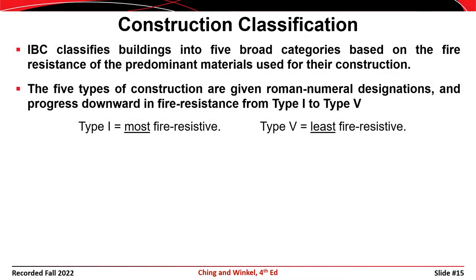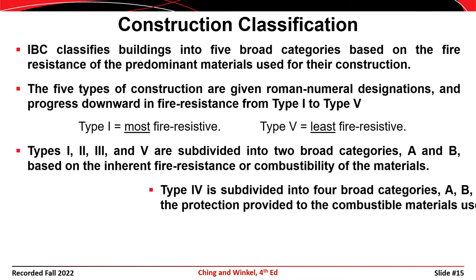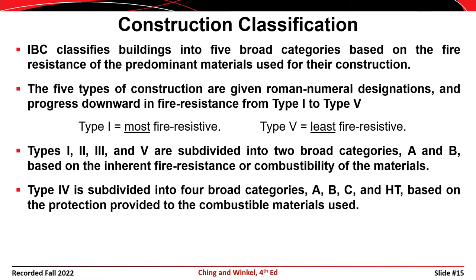The International Building Code includes five major types of construction, Types 1 through 5, with Type 1 being the most resistant to fire and Type 5 being the least resistant to fire. Each of these five main types is further subdivided into an A or B classification, except that Type 4 is subdivided into an A, B, C, or HT classification, resulting in 12 classes of construction with respect to fire resistance.